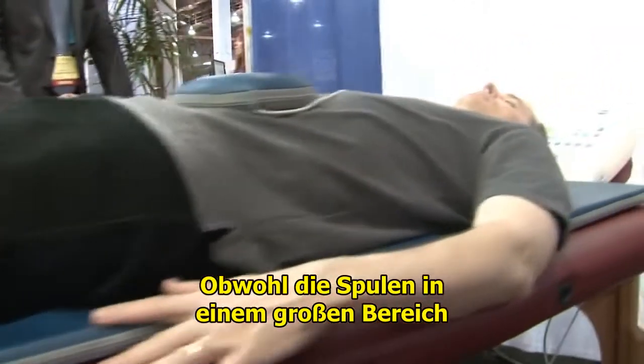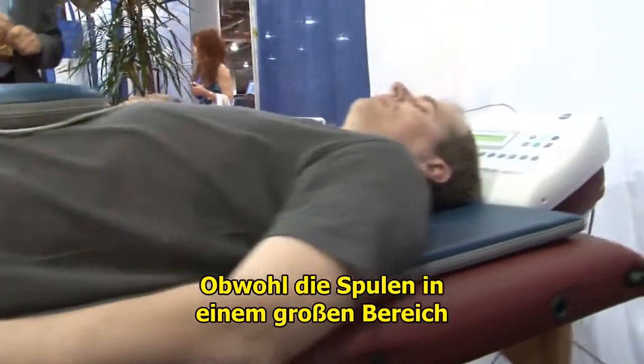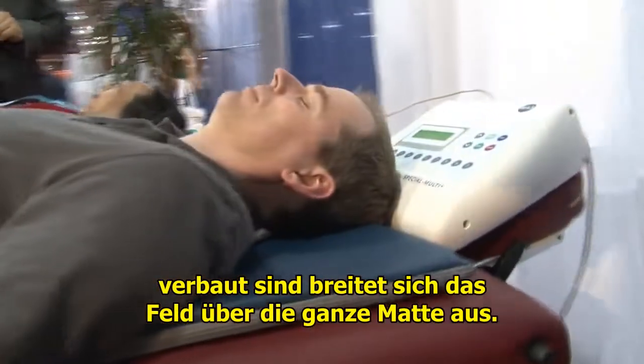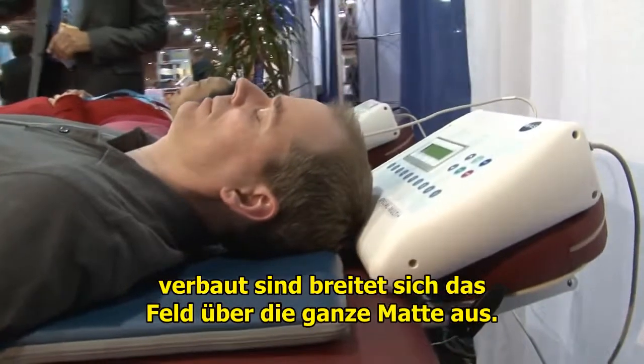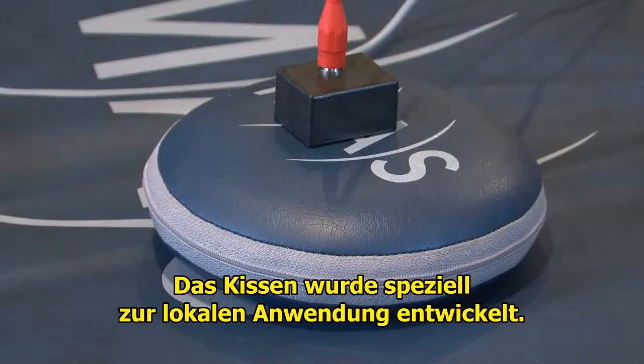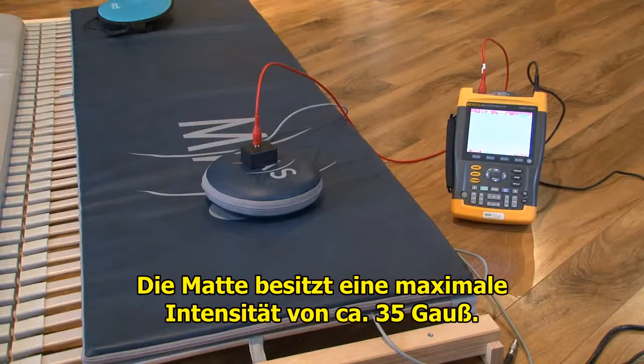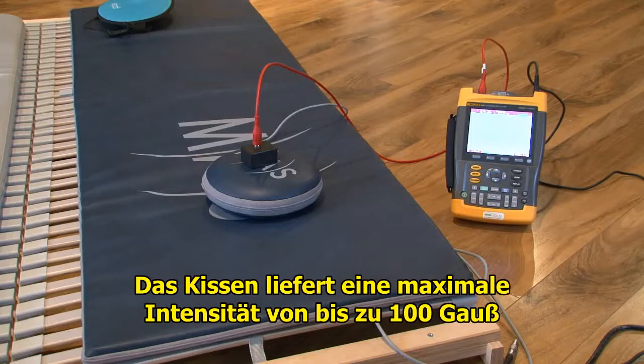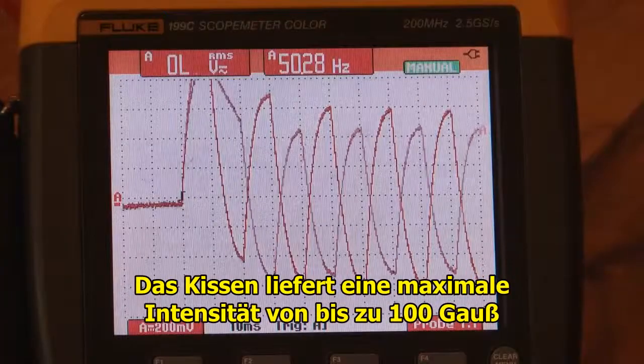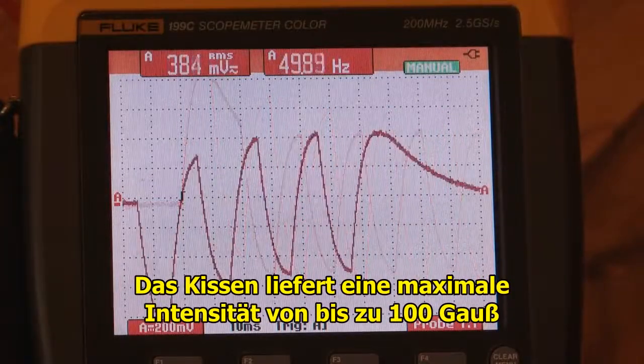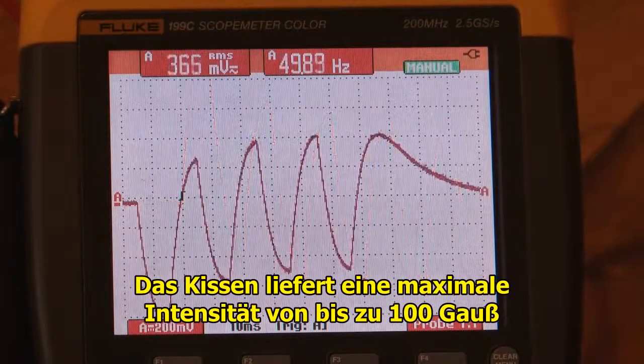Now, even though they're positioned in those areas, the magnetic field generated by them expands across the different coil sets. The coil itself, because of its size, is designed for local treatment. The whole body pad has a maximum intensity of about 35 Gauss. The pillow applicator tends to have an intensity, or can have an intensity, of a maximum of about 100 Gauss.